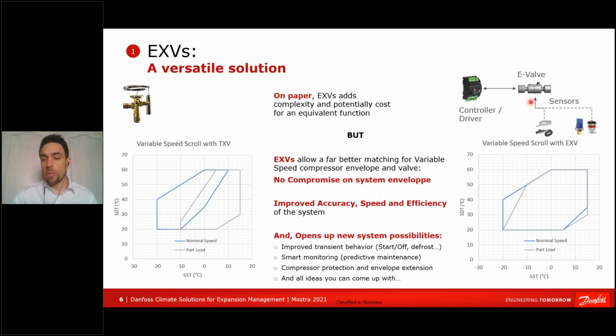So yes, on paper, it adds complexity. So why do that? Then you have to look at the envelope you have for different kinds of application. If you look at that envelope, this is a variable speed compressor envelope that is drawn for 2 different speeds. In gray, you have the very low speed, and in blue, you have the high speed. The envelope here is the compressor plus the valve, meaning that the valve, the thermostatic one, is probably limiting the capability of your machine to work efficiently at high speed and low speed.